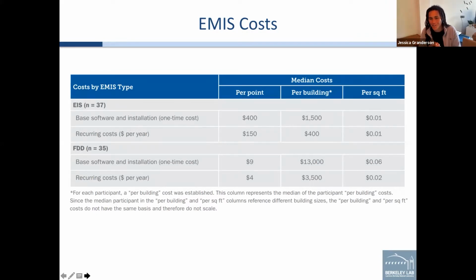At the end of the day, across these large portfolios, those ongoing costs come to either a penny a square foot median or 2 cents a square foot median - so things kind of normalize out. Remember that these costs are rapidly recouped, with a median payback of about 2 years, driven again by either 3% portfolio-wide savings on meter analytics and energy information systems, or 9% on fault diagnostics.